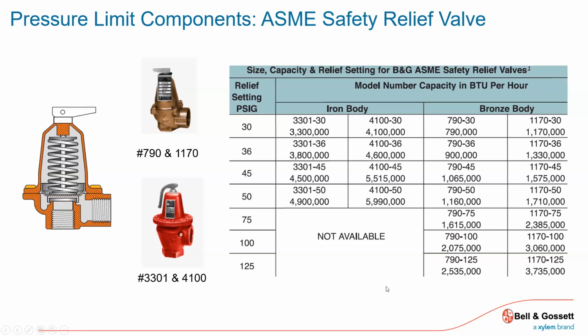Hey, I'm a 30-pound little cast iron sectional boiler in downtown Boston. Don't put a 50-pound valve on me just because you can. I haven't been tested. God forbid anything ever happened down there, and the insurance people come in and say, who the hell put a 50-pound valve on a boiler that's only been rated and tested by the manufacturer and the industry for 30? That's a serious problem. So you never want to play with that.